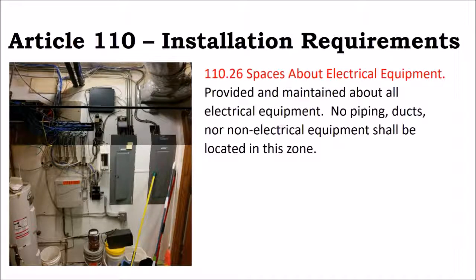And so the question is, well, is that air conditioning duct a code violation or not? You walk through the door, you see the service panel, you see other code violations, and you might look at that air conditioning duct and say, I wonder if that's a code violation too. And for that electric service panel, it might be that air conditioning duct is in fact 6.5 feet tall. And so from the floor up to 6.5 feet is 6.5 feet of clearance.